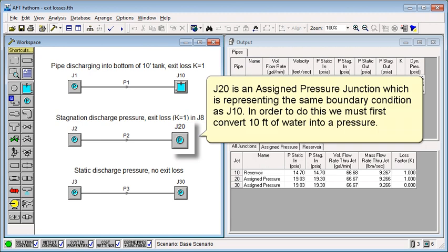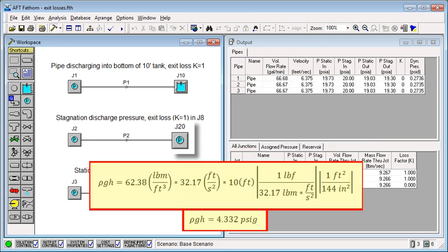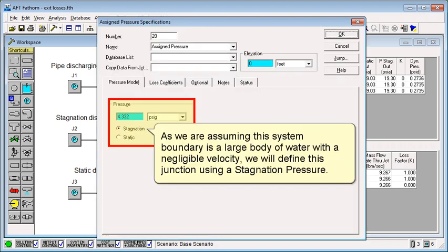J20 is an assigned pressure junction, which is representing the same boundary condition as J10. In order to do this, we must first convert 10 feet of water into a pressure. As we are assuming this system boundary is a large body of water with a negligible velocity, we will define this junction using a stagnation pressure.